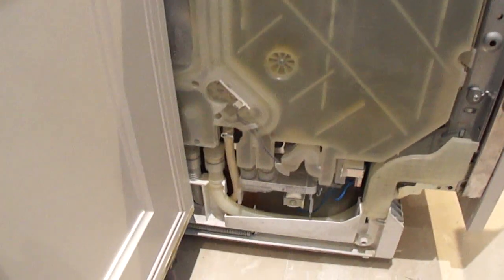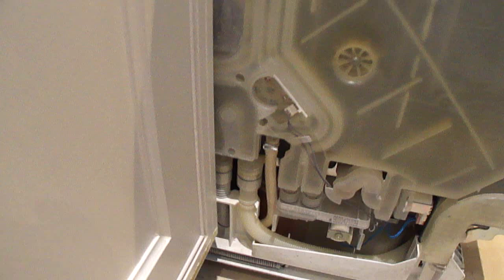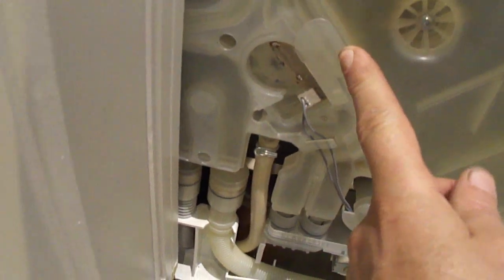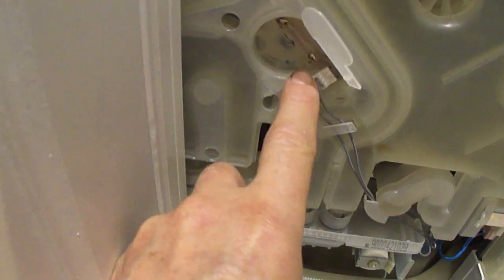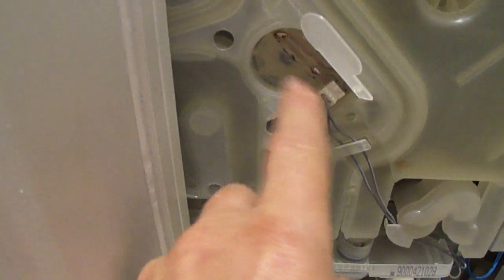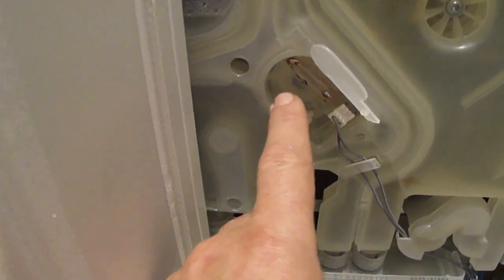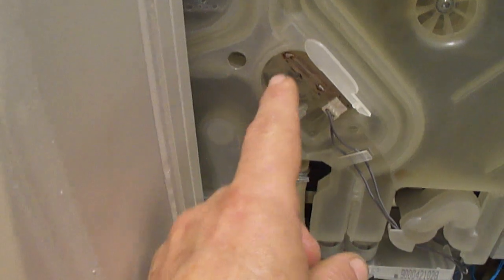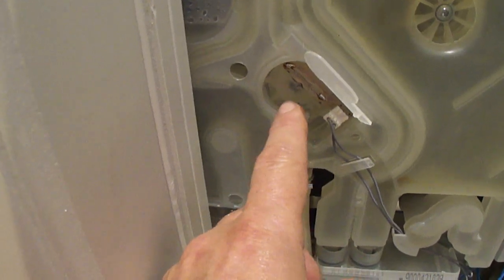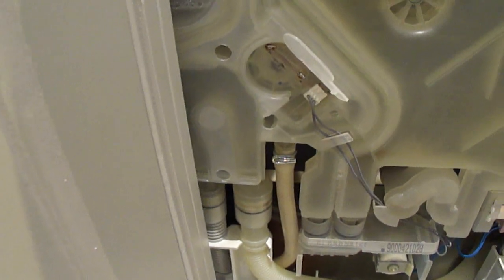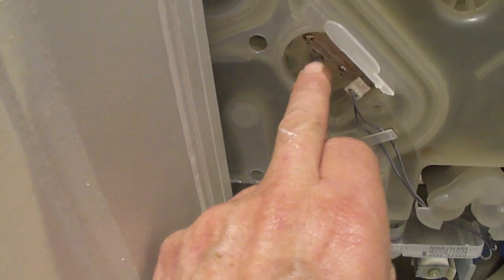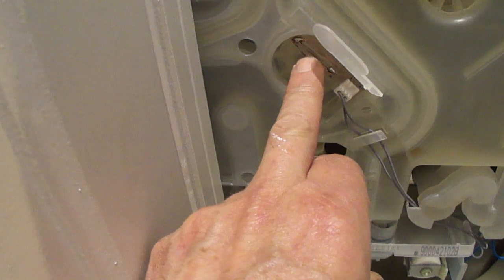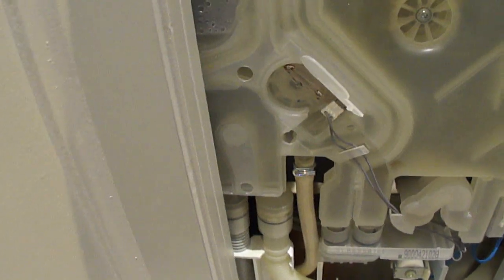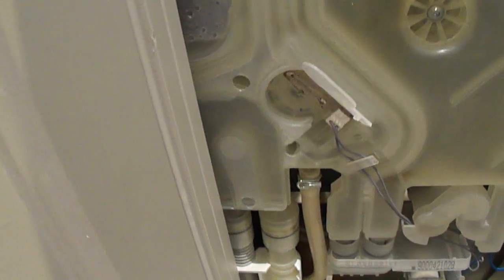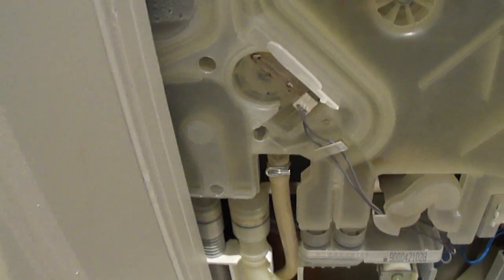So the flow control is very simple. It's this little reed switch in here. You can see that there's an impeller behind there which is on the water side, that's got a magnet in it, and when the water flows through there the impeller turns and it repeatedly opens and closes this reed switch. So this reed switch is normally open, and in contact with the magnet it goes closed.